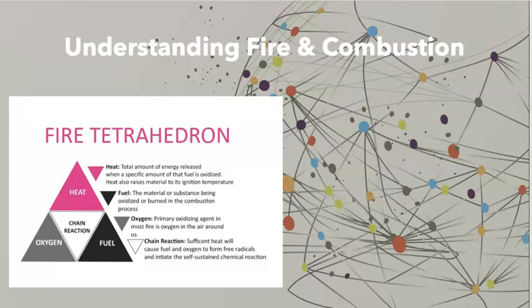While the fire triangle is pretty easy to comprehend, it's very easy to misunderstand or miscomprehend the fire tetrahedron. A lot of students in some of the projects that they do in my class think that halon or another product smother fire and take away the oxygen. They don't. CO2 does that.